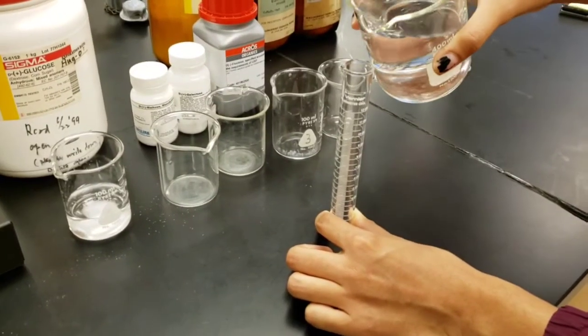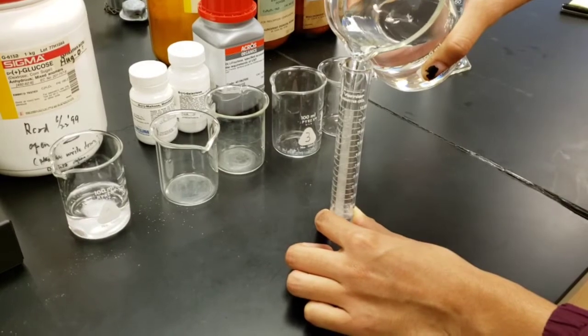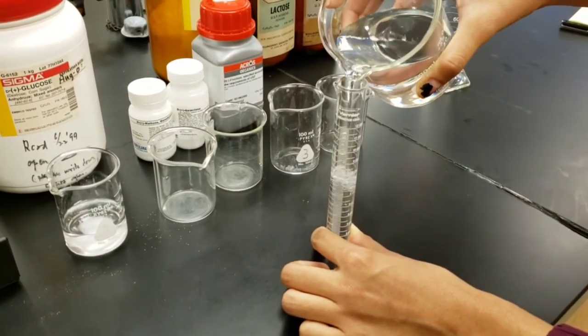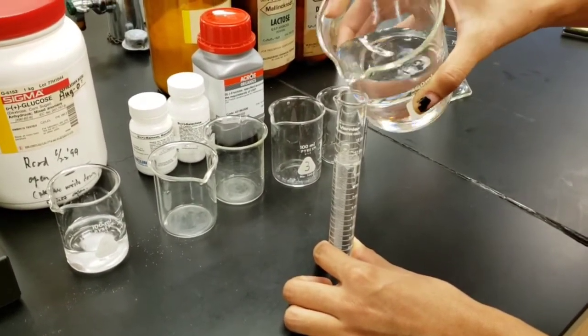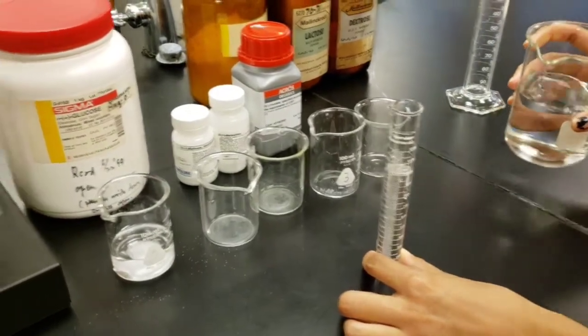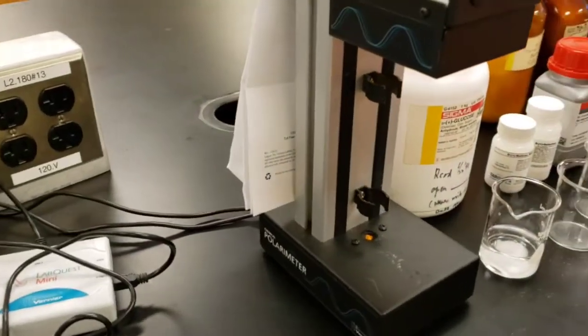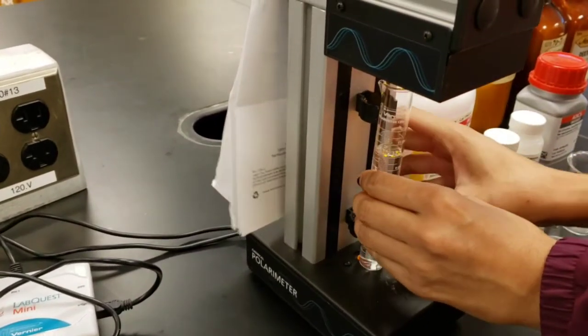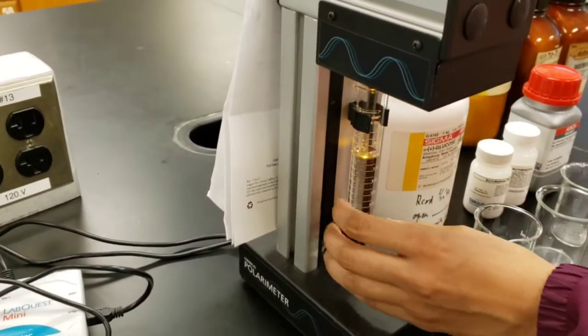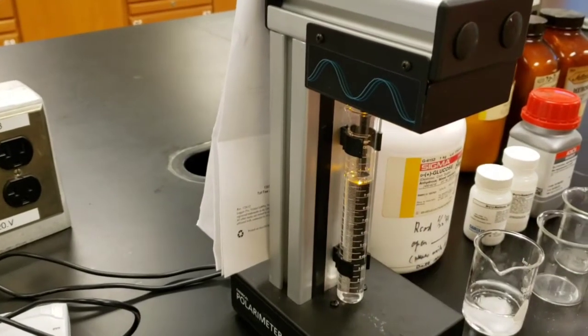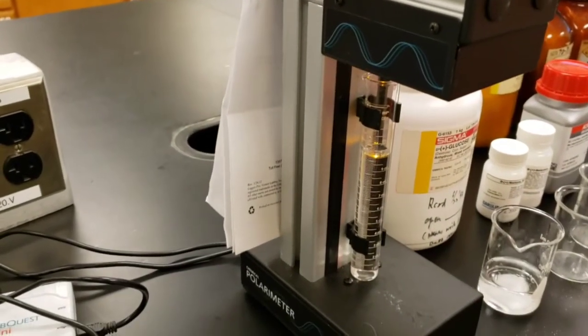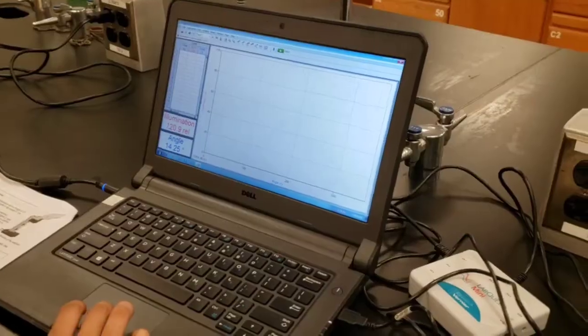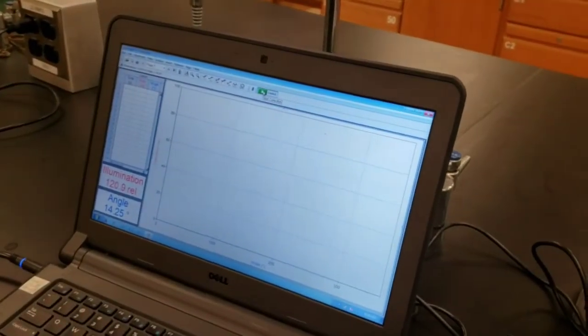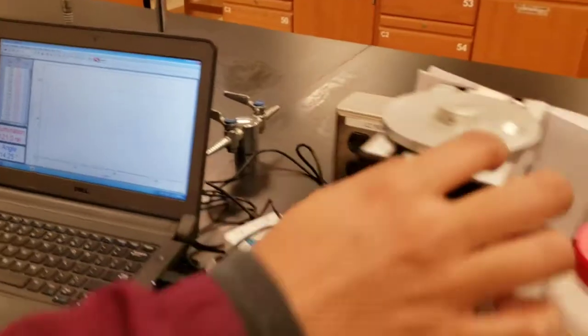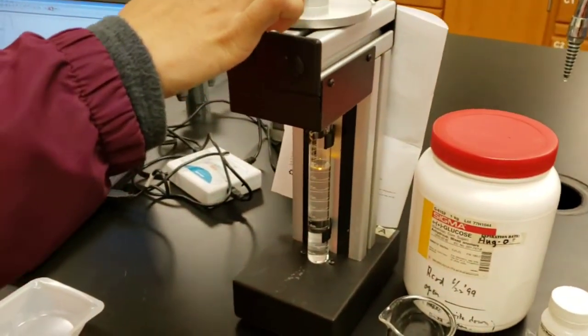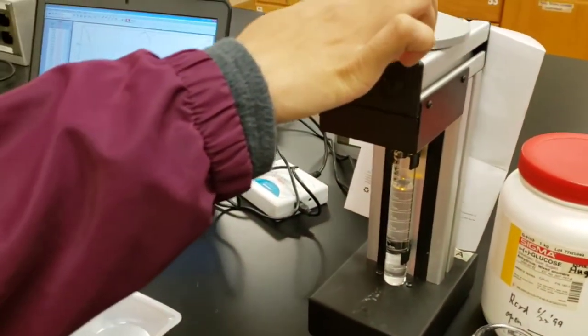We're going to calibrate the polarimeter by running pure distilled water. Fill the cell up to the 10 centimeter mark and then place it in the polarimeter. The 10 centimeter mark on this sample cell does not equal 10 milliliters. Calibrate the polarimeter by pressing collect on the software and then manually rotating the dial on the polarimeter.